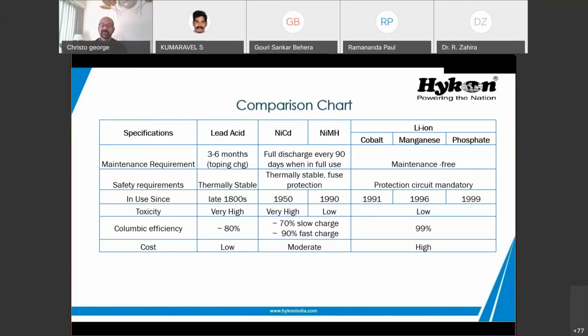And if you look at the cost right now, the lead acid battery is very low. Nickel cadmium is now at par with lithium ion battery, because the cost of lithium battery every year is dropping, by 10% for the last 5 years. If it continues like this, by next 2 years lithium battery cost will be at par with lead acid battery. Then there will be a huge replacement in the lead acid field, because it will disrupt that segment of battery manufacturing lead acid battery in the next 3 to 4 years.